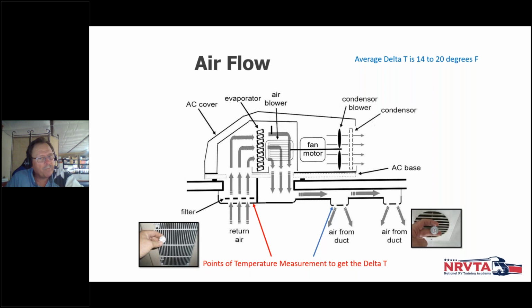Now we're going to take the second measurement, and we're going to find one of the diffusers where the ductwork dumps air into the compartment, the one closest to the air conditioner. The air coming out of that grill is going to be less hot. So maybe it went in at 85 and maybe it comes out, let's say, at 65. You're going to leave your thermometer in each location 3 to 5 minutes, and you take your readings and you can do your calculations.